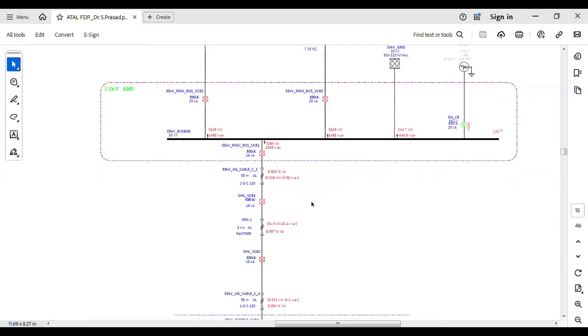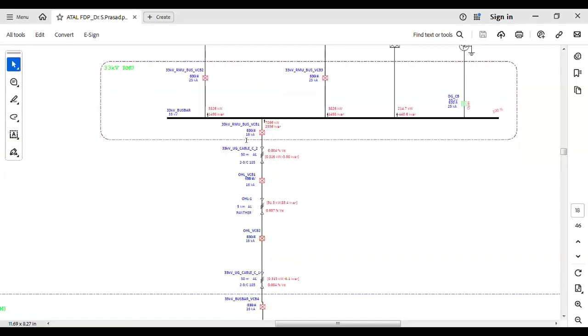Suppose you need to maintain 8.25 MVA at the POI as the contract demand. Though the plant capacity is 10 megawatt DC, the actual AC capacity is 8.25 MVA. But how much are you injecting at the point of interconnection? Suppose 7.8 megawatt. You have to see what the contract demand at the point of interconnection is. If it is 8.25, then you have to decide how much extra inverter capacity to install at the plant so that I can maintain the contract demand. So those kinds of analysis we are conducting during load flow.